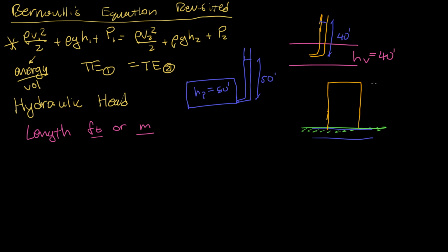And so the structure is 100 feet, and let's say that the city tells me that the water main has a total head, HT, of 75 feet. Well, I know immediately that this water is not going to be able to reach the top. It's going to reach 3/4 of the way. But I know that without having to do any kind of conversions, without having to plug numbers into any of my equations. Because I was given total head, I already know that it can't reach the top.